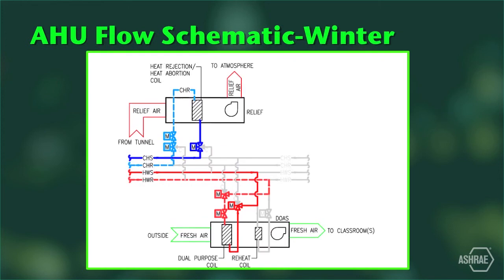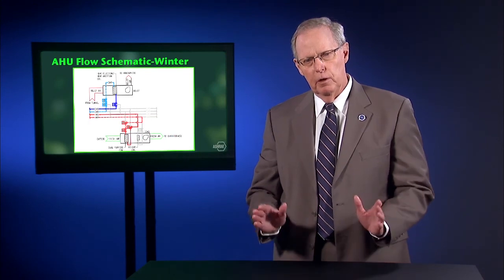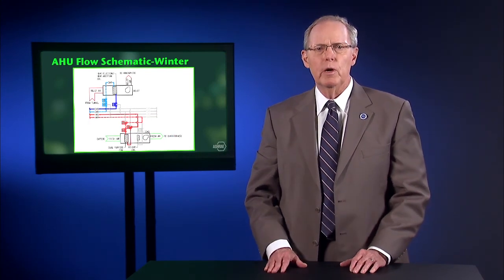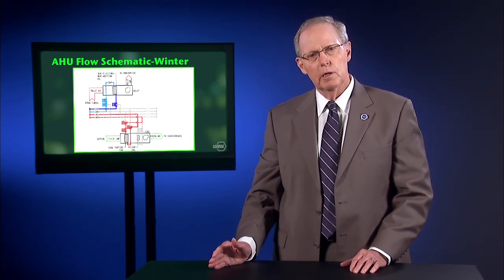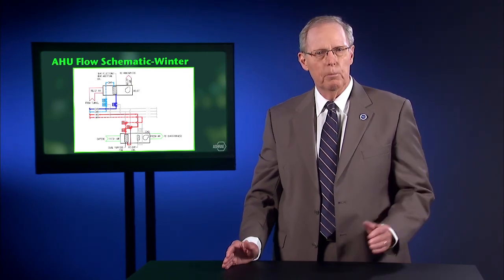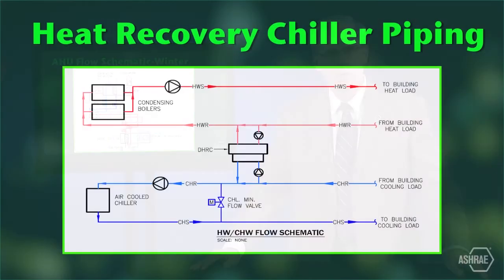This is the piping arrangement for the 2 units in winter. The 4 3-way valves have switched position. The DOAS primary coil is in heating, and the downstream reheat coil is off. And the relief unit coil is connected to the chilled water system. Now, if you were paying attention, and I hope you were, a legitimate question would be, why am I cooling the relief air in winter and warming it in summer? Well, we have a heat recovery chiller back in the mechanical room, and it's piped like this.